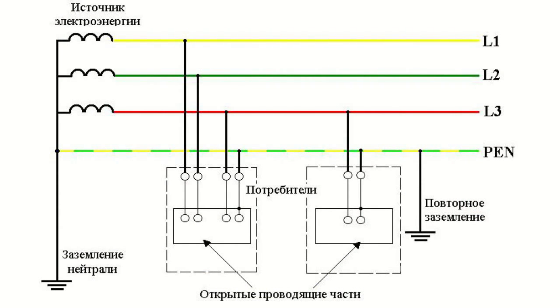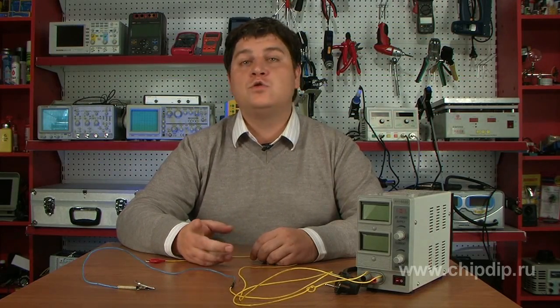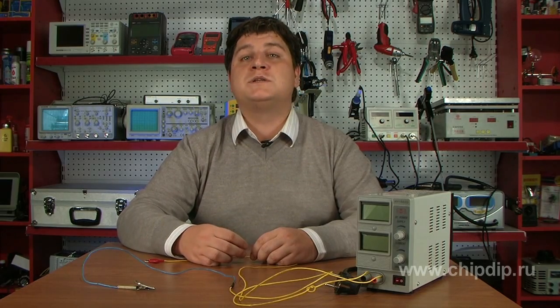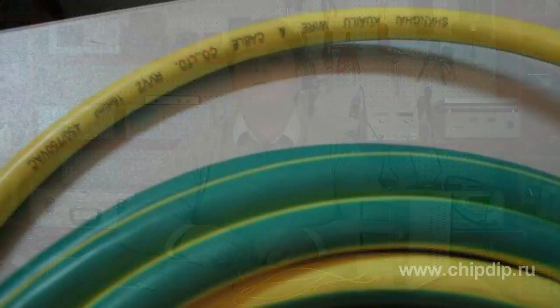In the TN-C-S system, the protective zero conductor is bonded to all the exposed non-current-carrying metal parts and can be grounded multiple times, while the working zero conductor should not be grounded. The equipment installation rules prescribe the use of green-yellow-stripe insulated wire for the protective conductor.